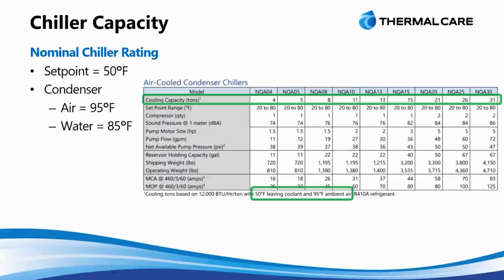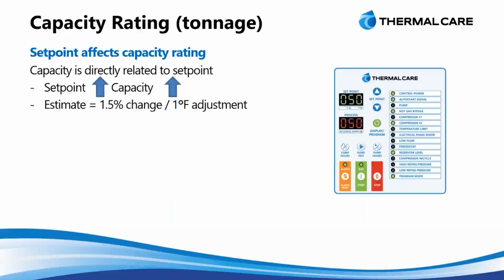We'll talk more about that, the 95 and 85, and how we're cooling the condenser of the chillers later in this. But to understand what we're talking about here, we just want to make sure that everything is being measured on a level playing field. So everybody out there that has a chiller, when they say a nominal chiller ton, they're using these same parameters. And so that way we're all talking about the same things. I bring up the nominal rating because we can do certain things that affect the capacity of the unit, and you need to be aware of those when you're selecting your chiller.